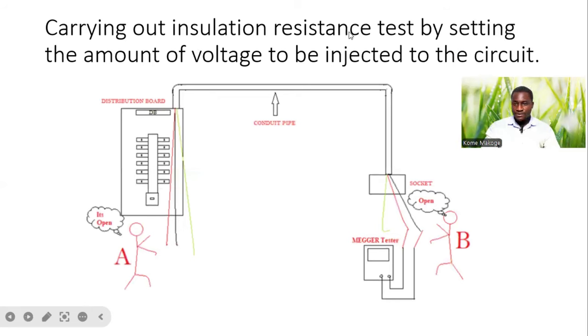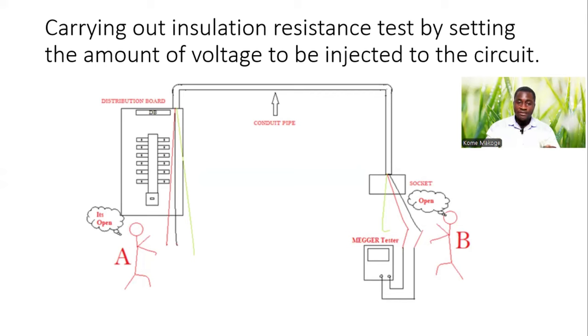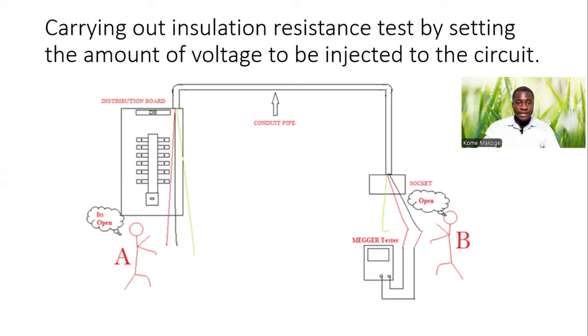Carrying out insulation resistance test by setting the amount of voltage to be injected to the circuit. The code says a DC voltage of not less than twice the supply voltage should be injected to that circuit. So if our panel board is 240 volts, the voltage to be injected will be not less than twice 240 volts. We select that amount on our selector range on the megger tester and inject it into the circuit.